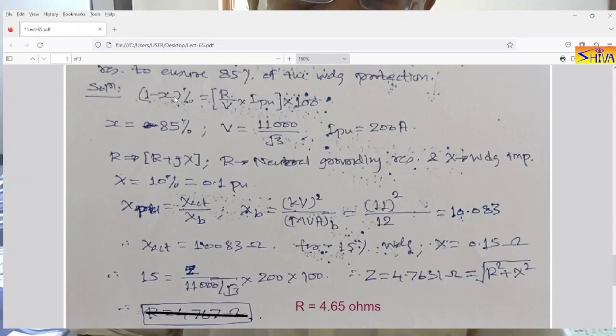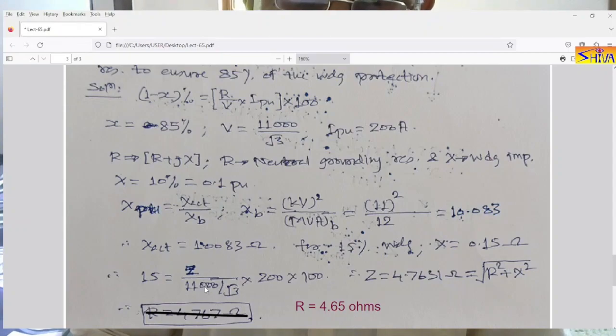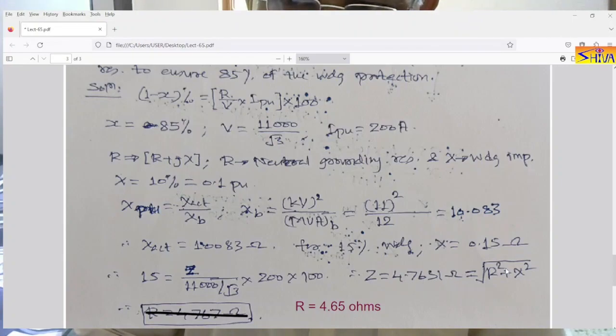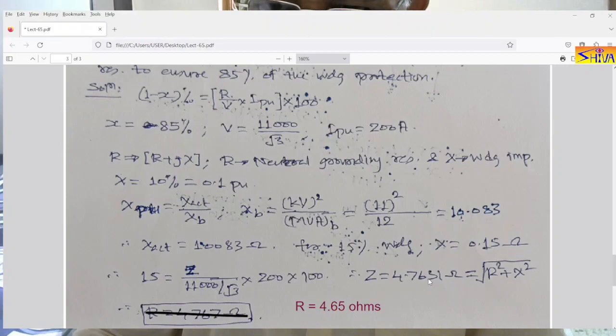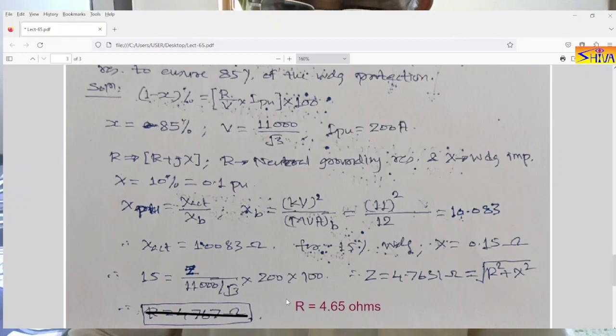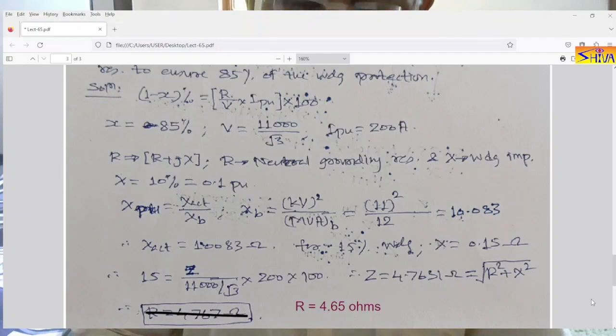Using the formula with 15% unprotected: 15 = Z / V × I_pickup × 100. With phase voltage = 11,000 / root 3 and I_pickup = 200 A, Z comes out to 4.7631 ohms. This Z consists of the neutral grounding resistance R and the 15% winding reactance of 0.15 ohms. So: 4.76 = sqrt(R² + 0.15²). Solving, R = 4.65 ohms. The resistance connected in the neutral grounding circuit is 4.65 ohms, and together with the winding reactance of 0.15 ohms, we achieve protection of 85% of the winding.